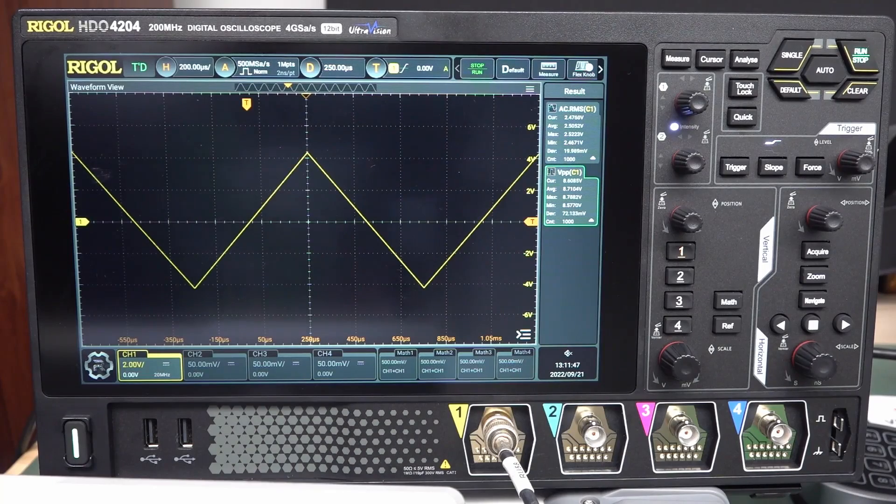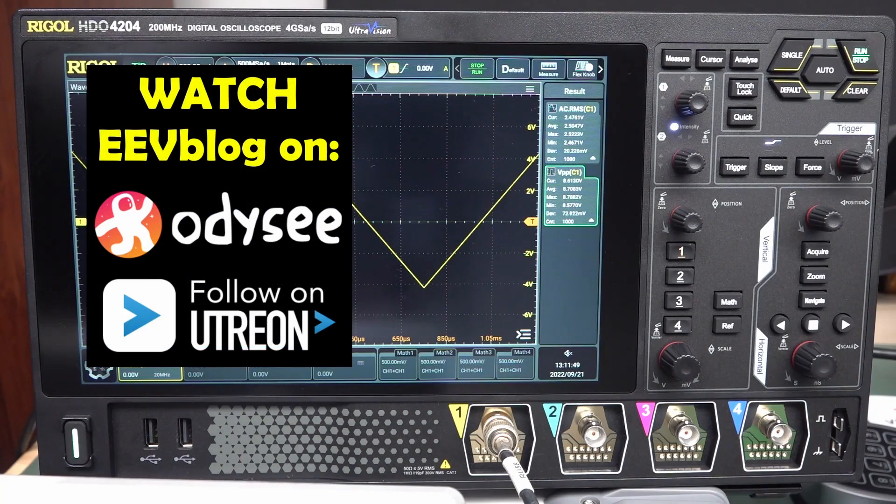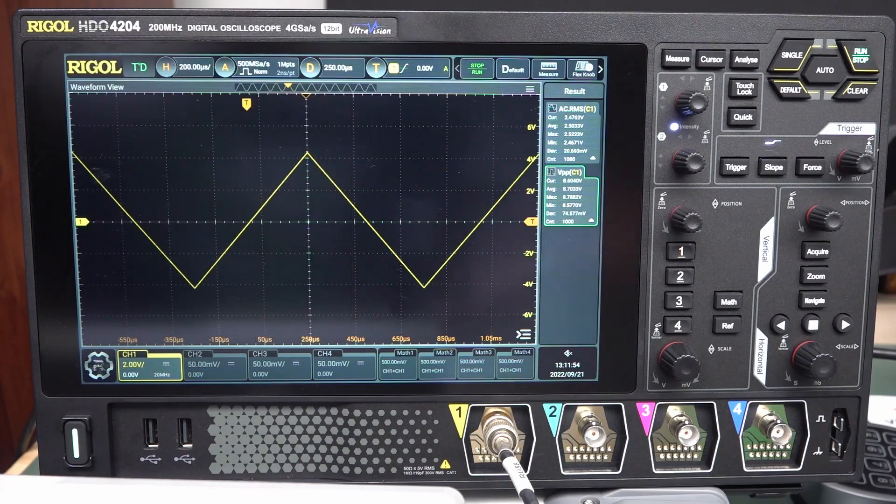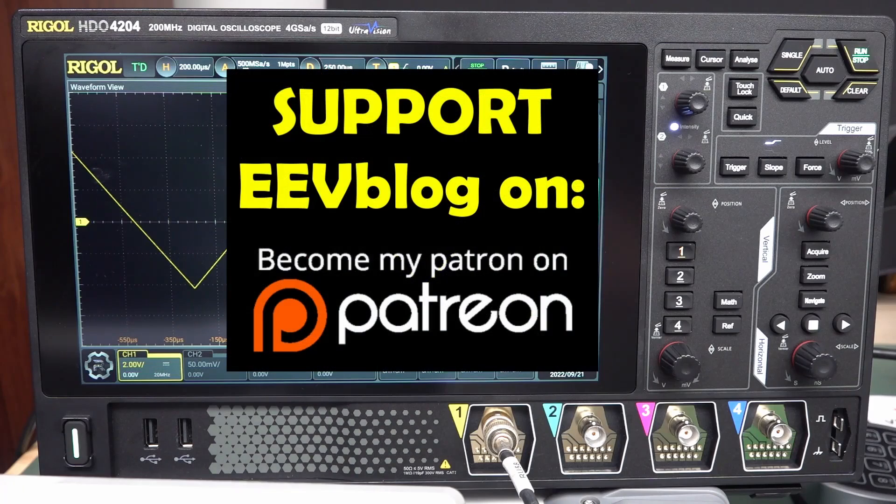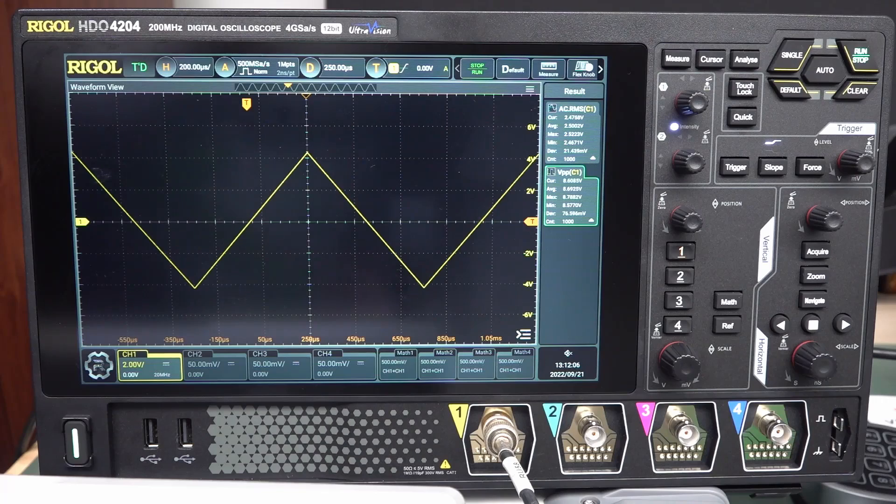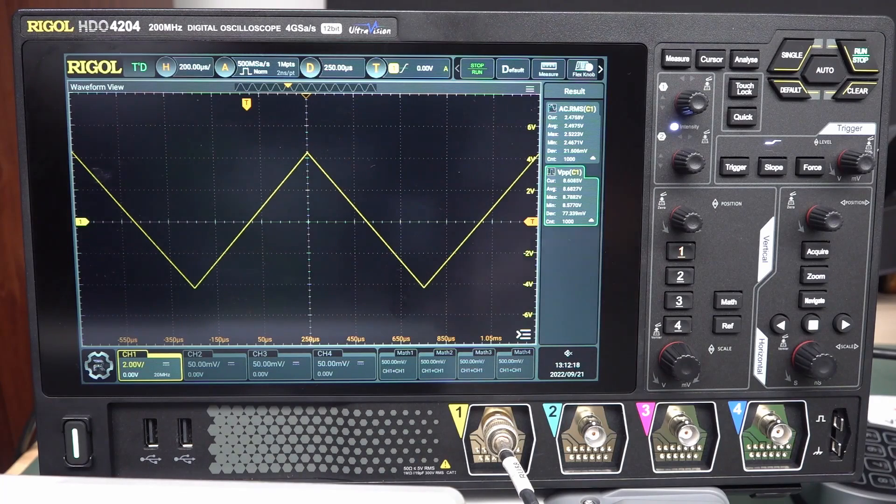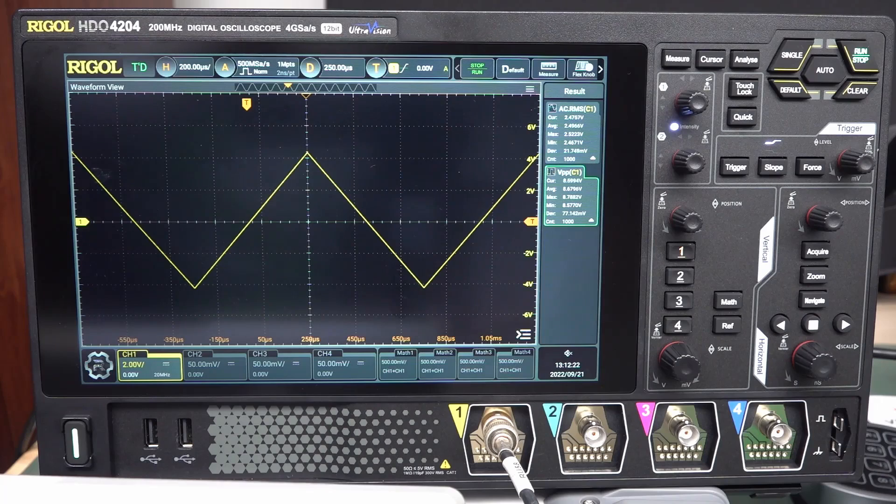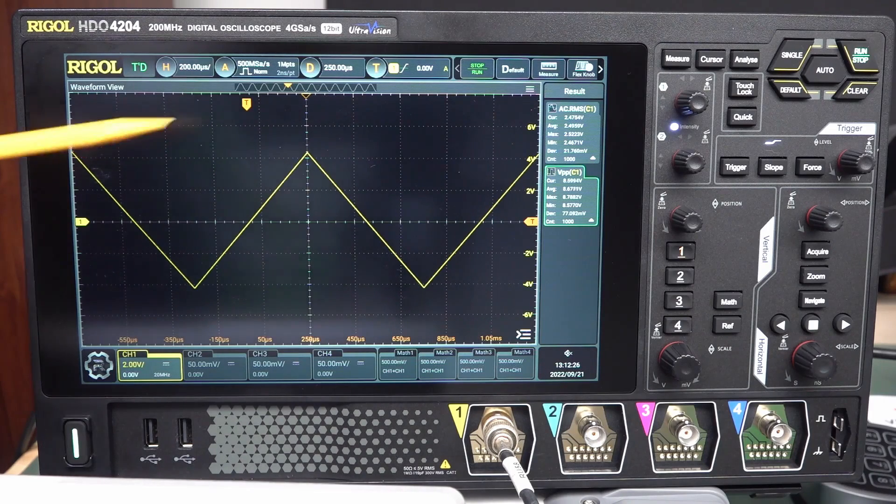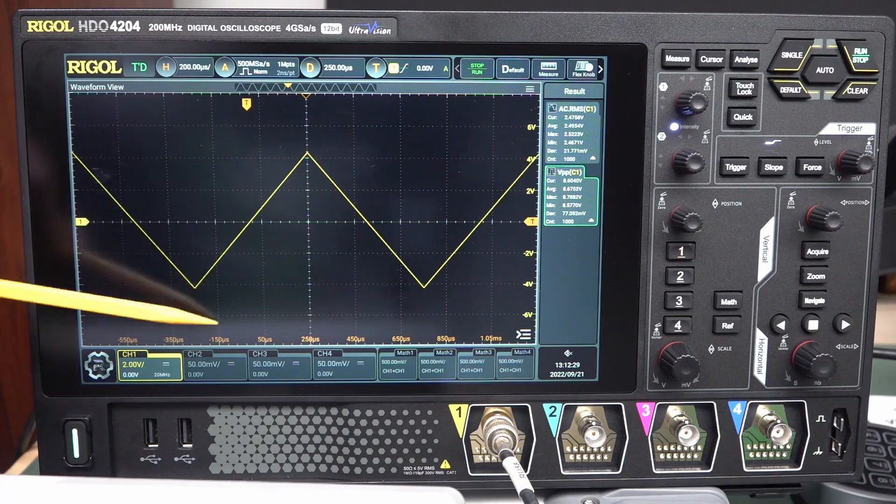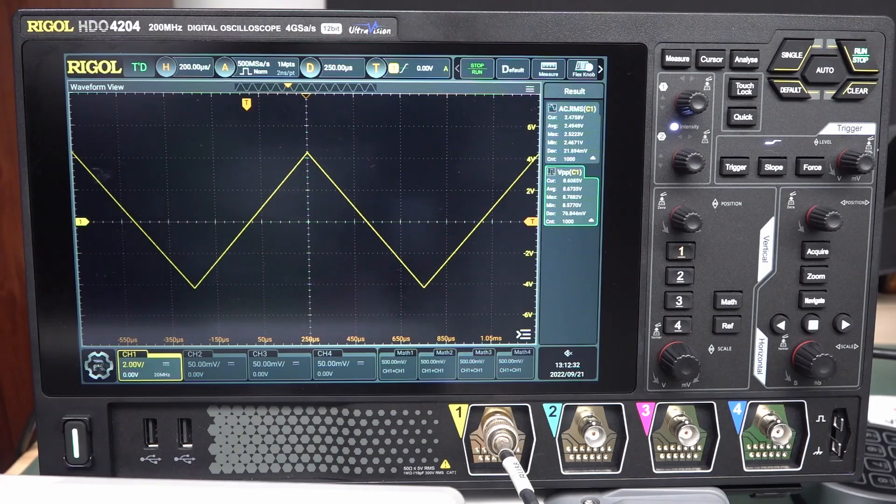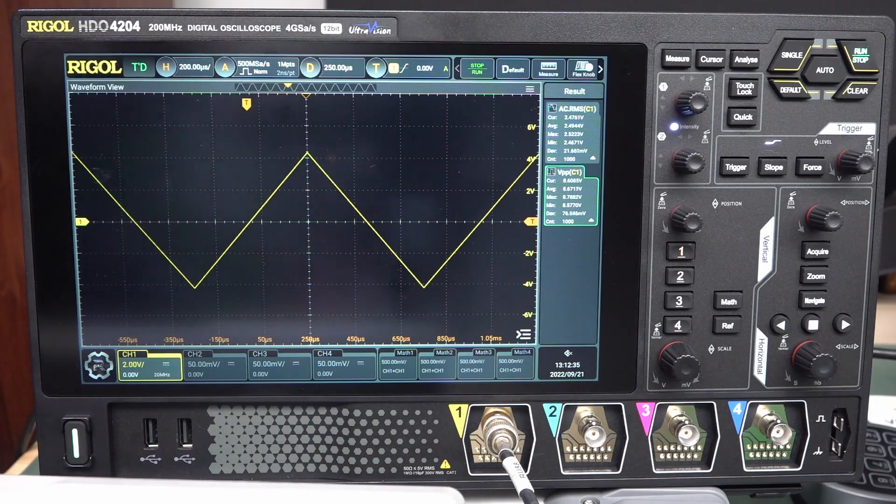Hi, I'm going to show you how to measure the dynamic range of an oscilloscope. This might be important because when you're analyzing, especially if you're a nerd on the EEVblog forum and you want to compare oscilloscopes, especially a 12-bit one like this new Rigol HDO 4000 series, you have to make sure you're doing apples-to-apples comparison. One of the things you need to know is, what is the full-scale analog-to-digital converter range inside the scope? What's it actually doing? So how do you measure that?